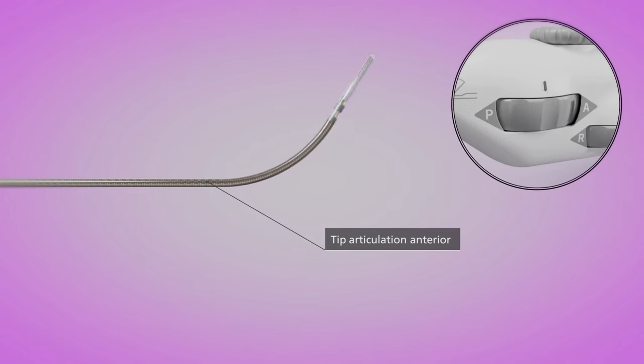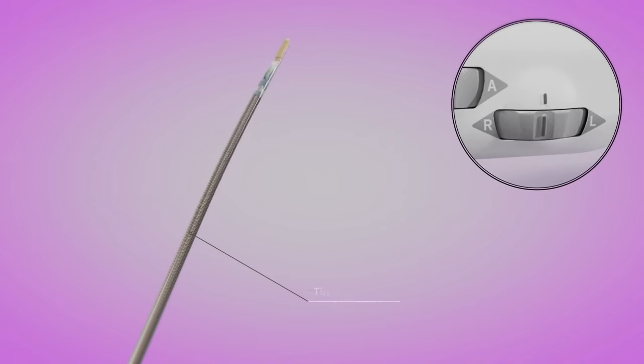With a 120 degree deflection range in all four directions and a 7.5 cm articulating segment, the catheter is very responsive and only requires minimal adjustments to navigate to the desired location.